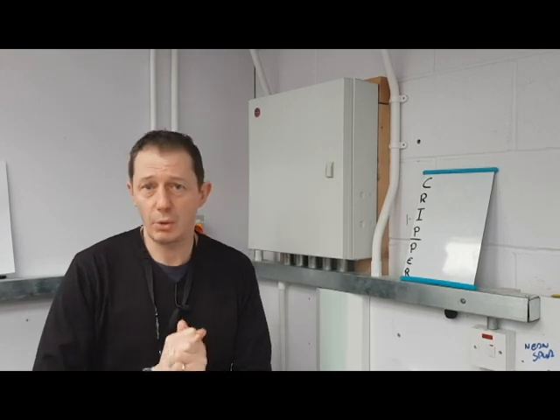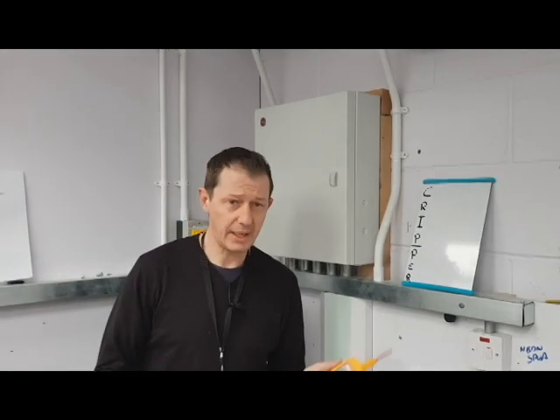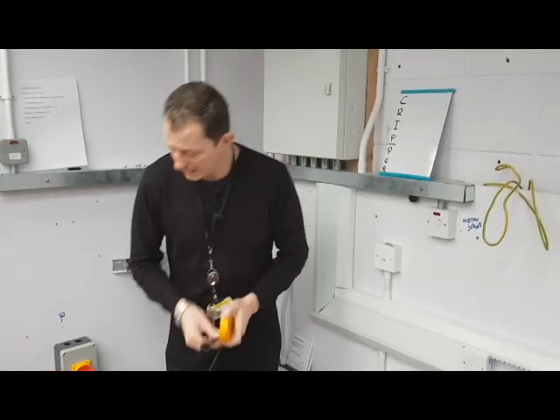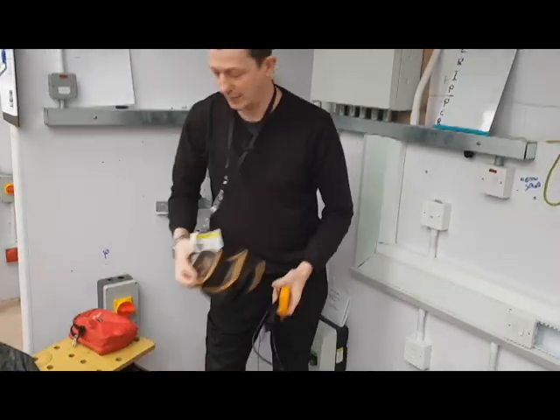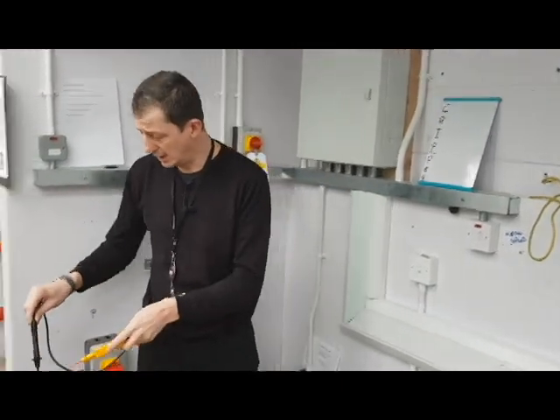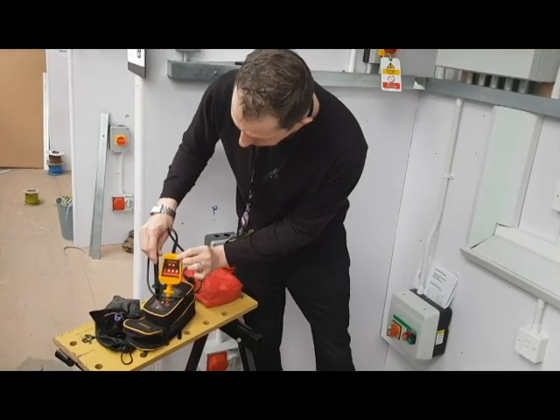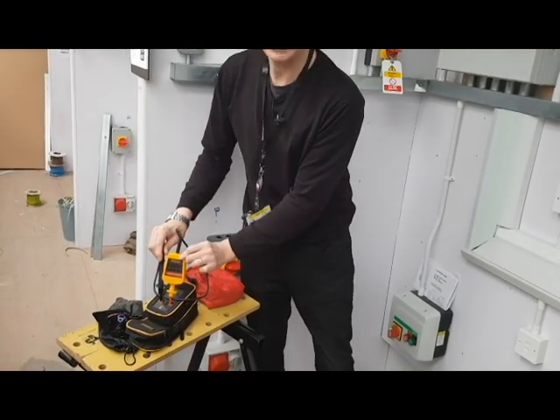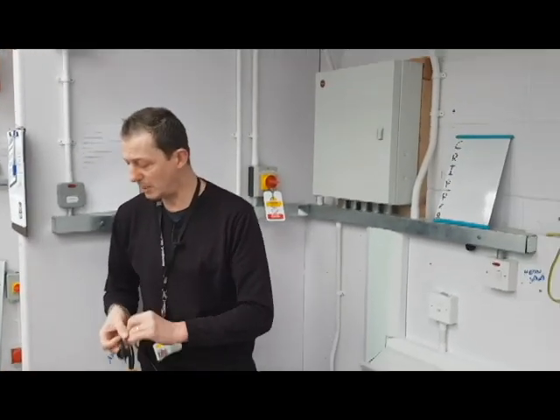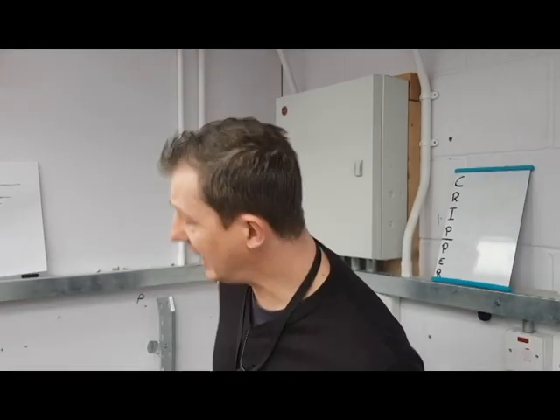Then what we need to do is get a voltage indicator, which I have here, and a proof unit, which we also have here. We need to prove that our testers work — simply put them into the proof unit. As you can see, they're all working fine, so our proof unit and indicators are confirmed working.